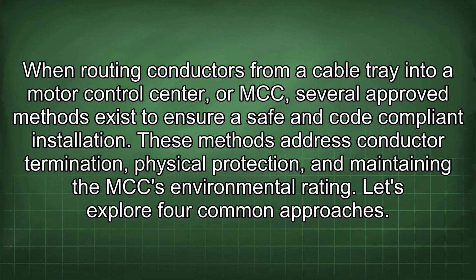When routing conductors from a cable tray into a motor control center, or MCC, several approved methods exist to ensure safe and code-compliant installation. These methods address conductor termination, physical protection, and maintaining the MCC environmental rating. Let's explore 4 common approaches.